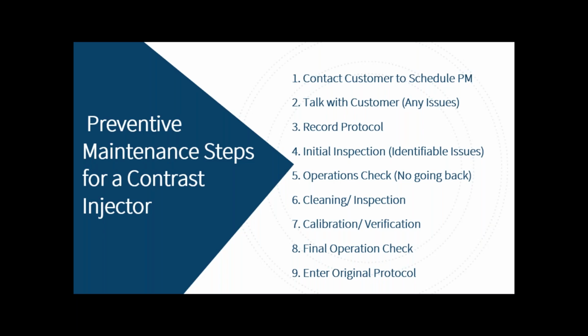Preventive maintenance steps for a contrast injector. Contact customer to schedule the PM. Talk with the customer. Record the protocol. Initial inspection: identifiable issues before you start your PM. Operations check. Once you start, there's no going back. Cleaning inspection. Calibration verification. Final operations check. And entering the original protocol.